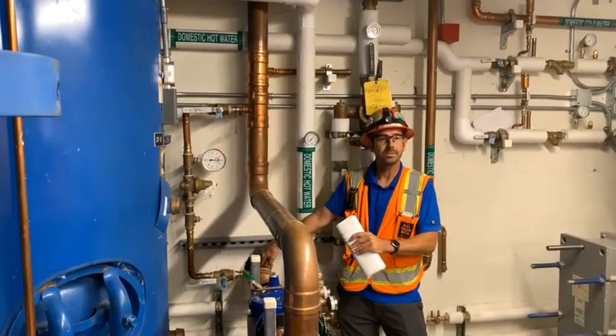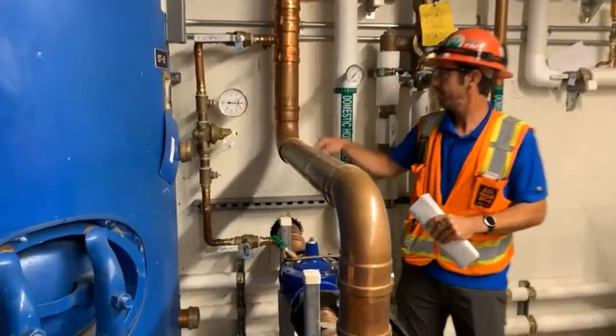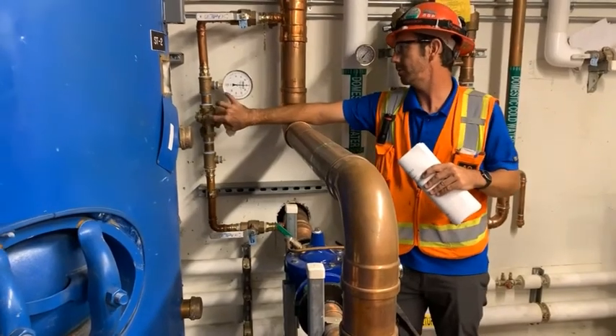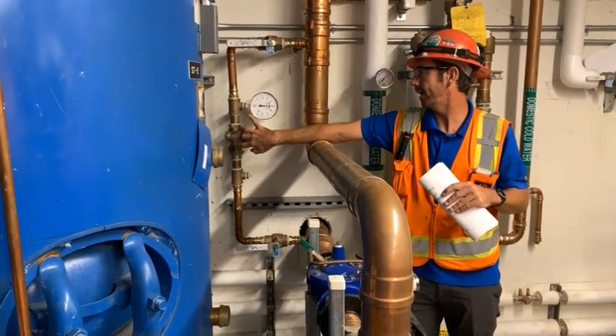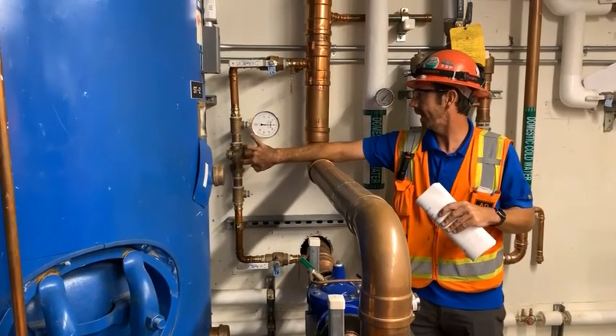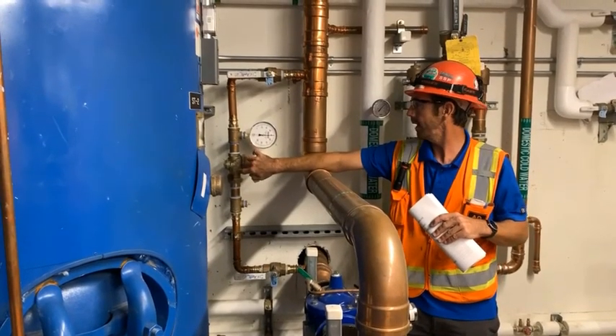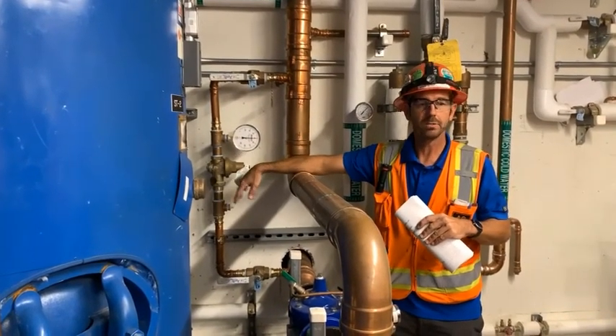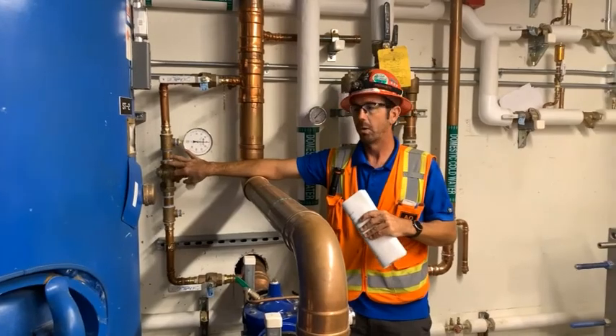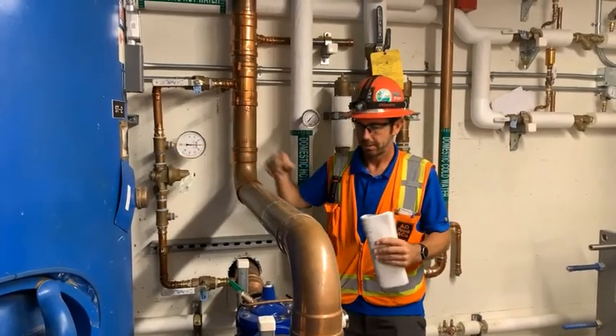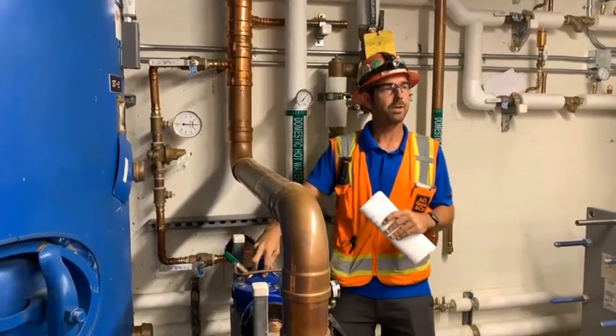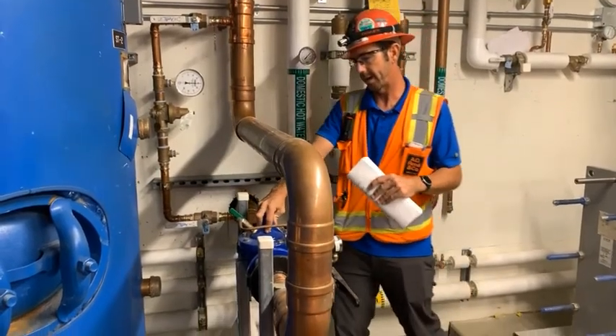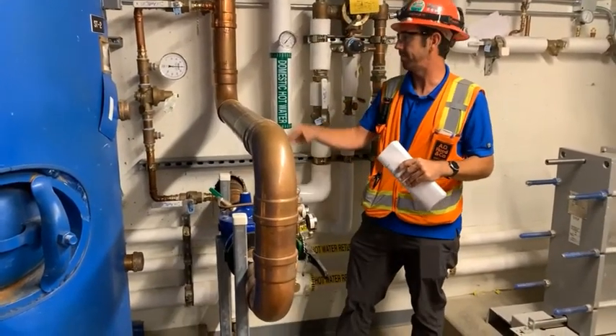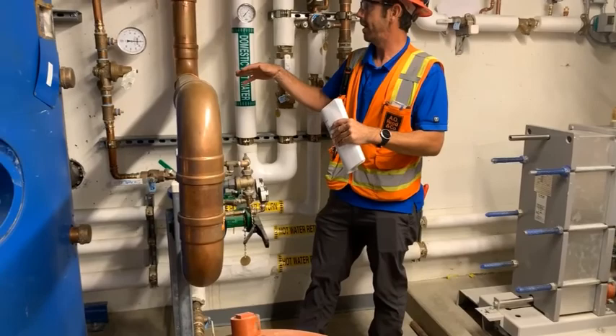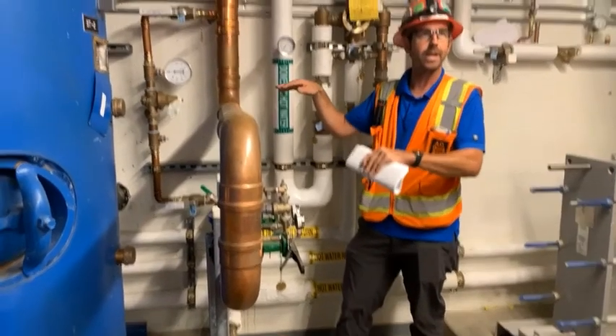We have 2 pressure reducing stations. We have a high and a low flow. So during low flow conditions, we'll run water through this regulator right here. We're set at roughly 80 pounds. Okay, so in a low demand, most of the water will run through this regulator. Once the pressure keeps dropping, then we'll start opening our main high flow regulator right here. This is set at 70, so it's 80, 70. You want them roughly 10 pounds apart. That way the regs aren't fighting each other where that set point should be, okay?